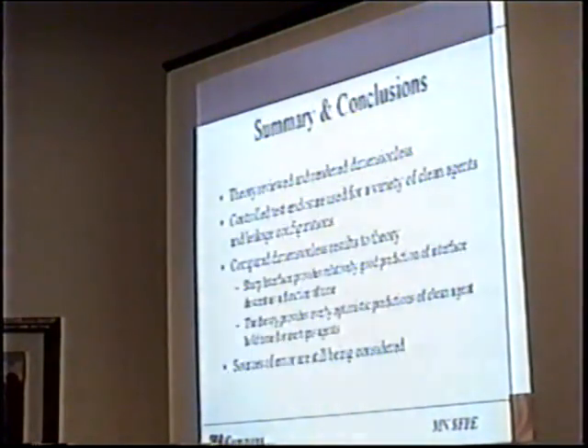Once again, a little bit higher scattered here, 13.8 for the RMS error, HFC 125. But for the most part, we've apparently modeled it very nicely with some pretty drastic assumptions in the mathematics of the model. And if we go ahead and throw all those dots together, the cumulative error is 28.5. It's not horrible considering that some things in the fire protection world are acceptable level of error maybe between 30 and 200% depending on what we're modeling. So it's not horrible. To the eye it actually looks very good.